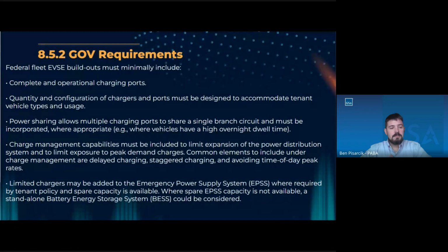Moving on, power sharing allows multiple charging ports to share a single branch circuit. We spoke about that a little bit earlier. That's the most efficient way to charge, assuming that meets the need. Charge management capabilities must be included to limit the expansion of the power distribution system and limit the exposure to peak demand charges. Common elements under charge management are delayed charging, staggered charging, and avoiding time of day peak rates. Jeff spoke about that earlier, but if you can charge overnight, and share that charger between multiple vehicles and have ample charge for the next day to do your job, that's the way to go, as opposed to plugging in at 4 o'clock in the afternoon on a hot summer day, because those would be high peak demands.